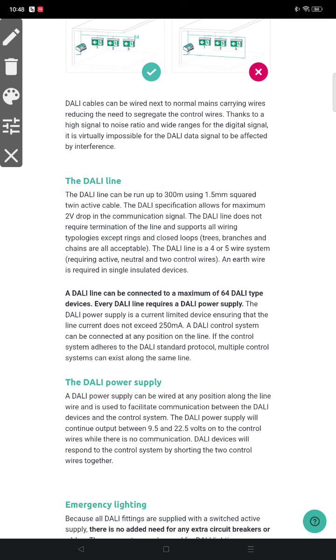The DALI specifications allow a maximum 2-volt drop in the communication signals. The DALI line does not require termination and supports all wiring and topologies except ring and closed loop. Trees, branches and chains are all acceptable. So you can do a tree, this is our tree, or you can do others too, like branches and chains.